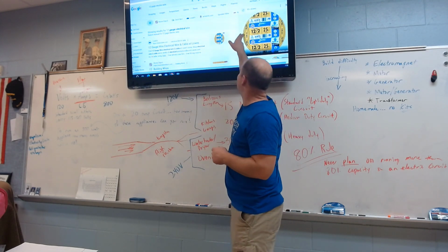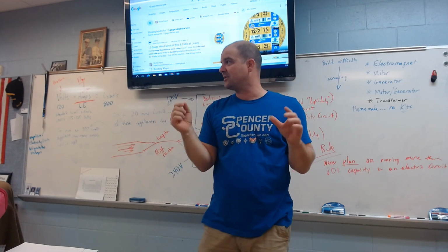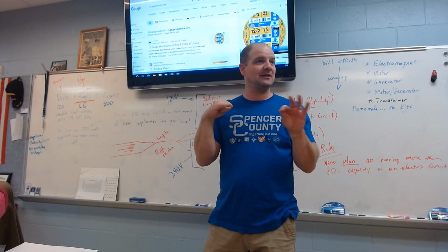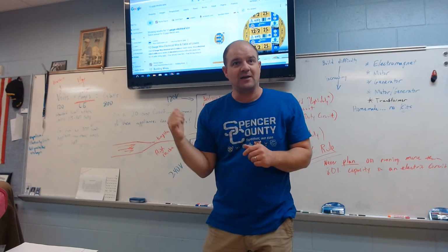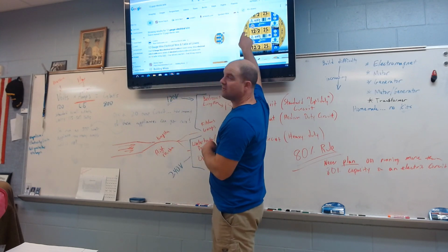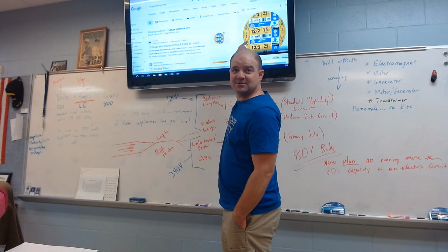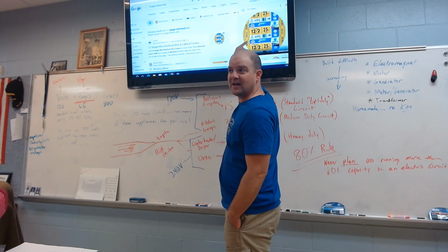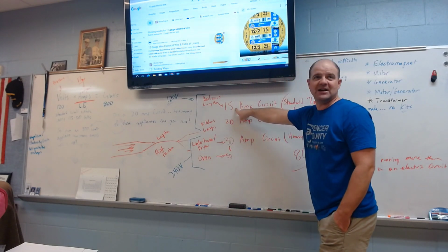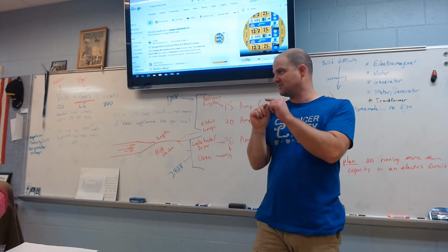And then inside of the plastic, inside of the paper, there's a plain, uninsulated ground wire. It's just copper, right? And then there's a white insulated copper wire. That's your neutral. And there's a black, which is your hot, okay? So all of those, this is 12 gauge, all right? It's the thickness of the wire. You can push 20 amps through this before it fails. Does that make sense? Okay. If you have a 15 amp circuit, you could get 14 gauge. It's a little bit thinner. It's a bigger number, but it means it's thinner wire, okay?